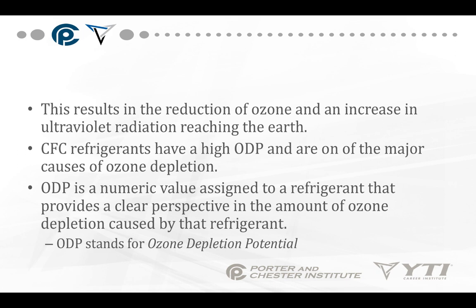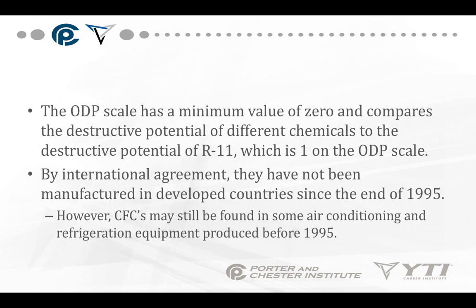The resulting reduction of ozone is an increase in ultraviolet radiation reaching the earth. CFC refrigerants have a high ozone depletion potential, ODP — another term you need to know. ODP is a numeric value assigned to the refrigerant that provides a clear perspective on the amount of ozone depletion caused by that refrigerant. The ODP scale has a minimum value of zero. R11 is rated 1 on the ODP scale. By international agreement, CFCs have not been manufactured in developed countries since about the end of 1995. CFCs can still be found in air conditioning and refrigeration equipment produced before 1995, so be very careful when looking at nameplates. Find the year manufactured — if it's before 1995, you may have a CFC. Do not mix it.